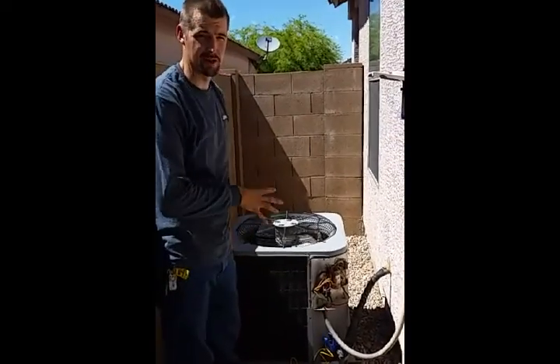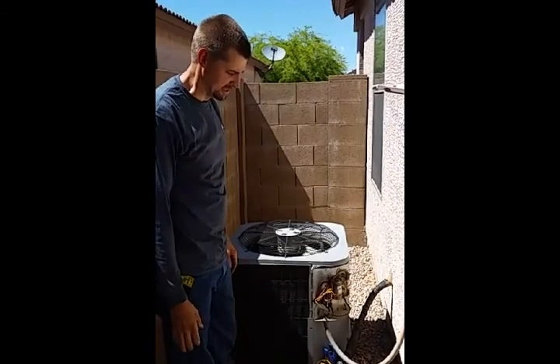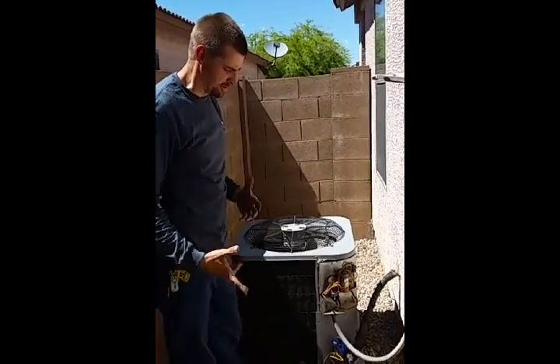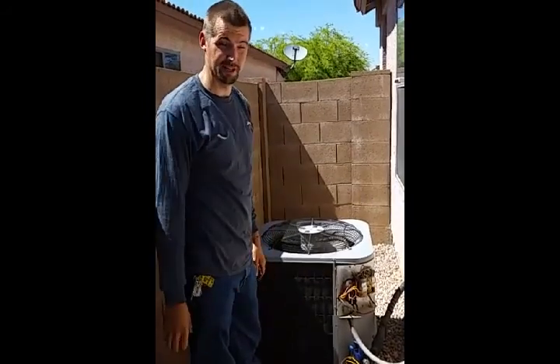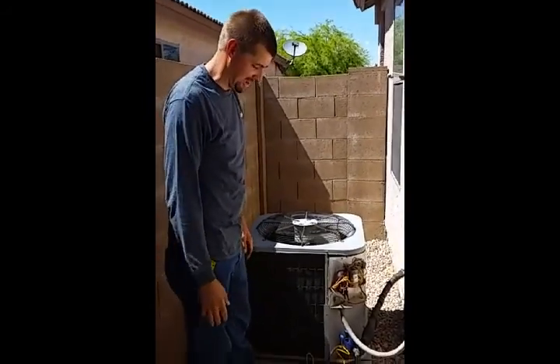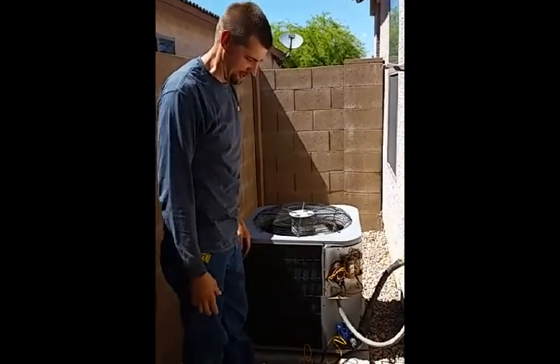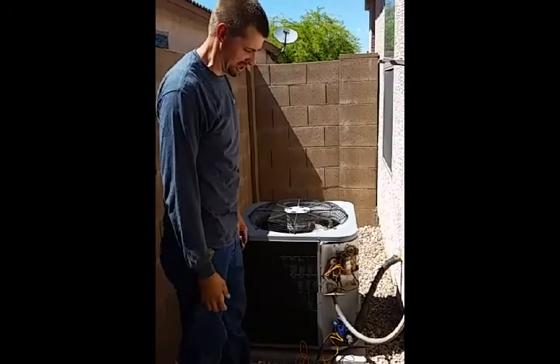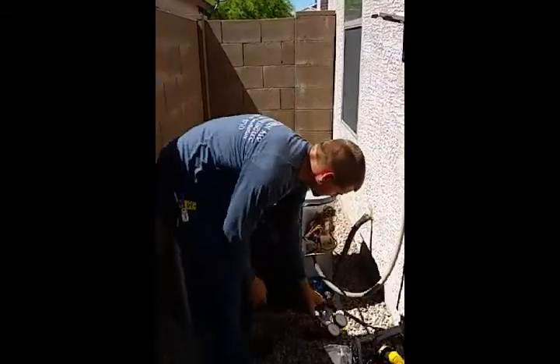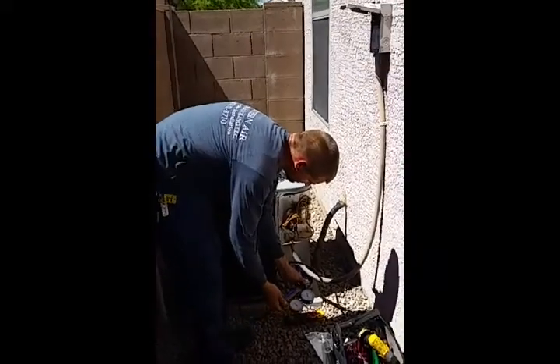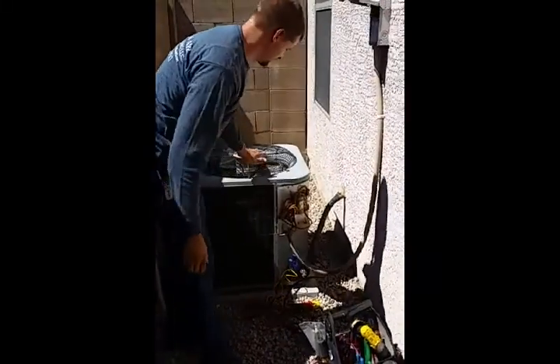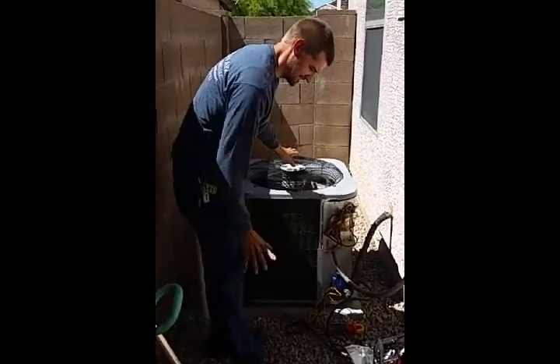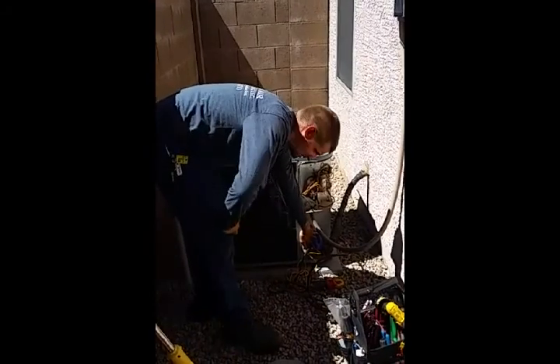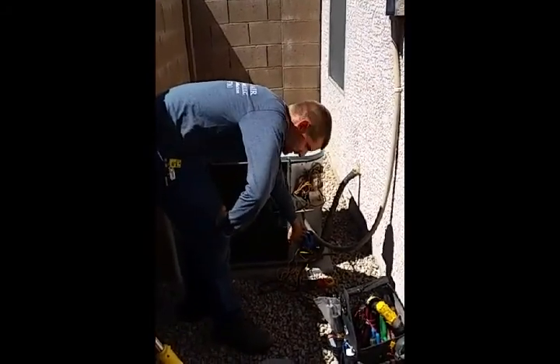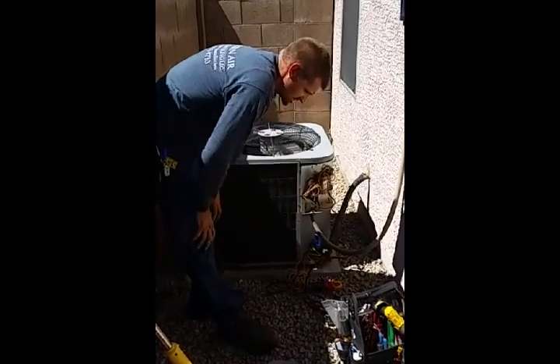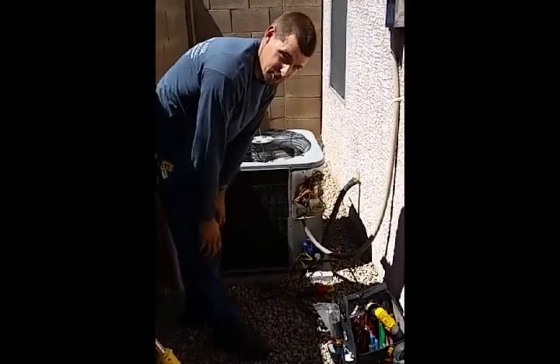Now this is an R22 system, so during the hottest part of the day, you're probably looking anywhere from about 10 to 15 degrees of superheat. Give it a minute and we will know exactly what it is doing at that point. Got hot air coming out, which is always a good sign. My line coming back from the air handler is nice and cold. Those are some real quick checkouts if you're ever worried about your system.